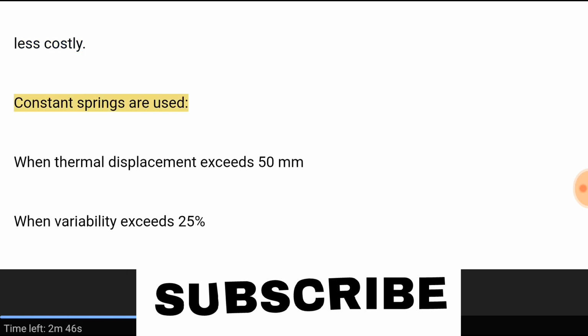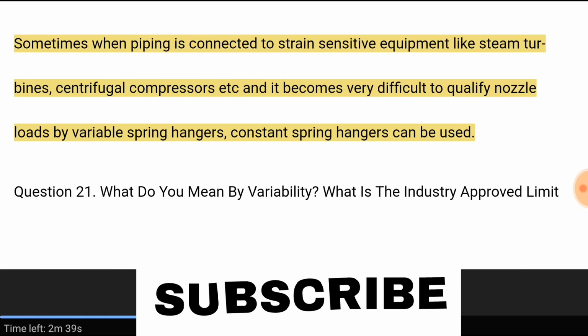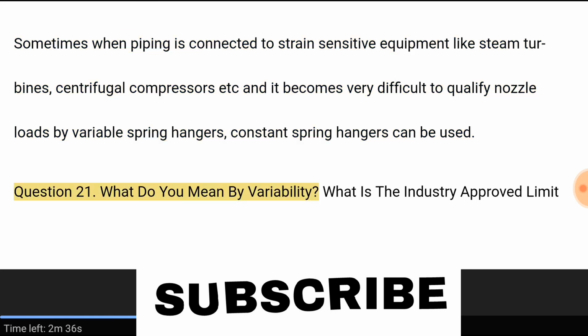Constant springs are used when thermal displacement exceeds 50 mm, or when variability exceeds 25%. Sometimes when piping is connected to strain-sensitive equipment like steam turbines, centrifugal compressors etc., and it becomes very difficult to qualify nozzle loads by variable spring hangers, constant spring hangers can be used.